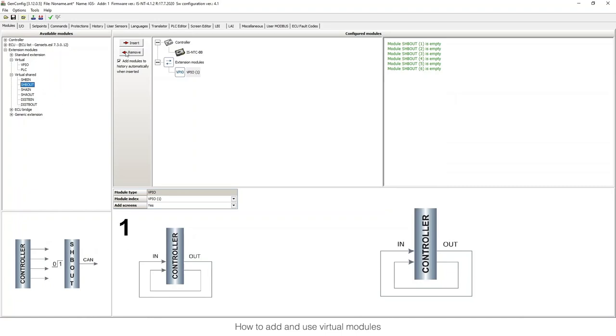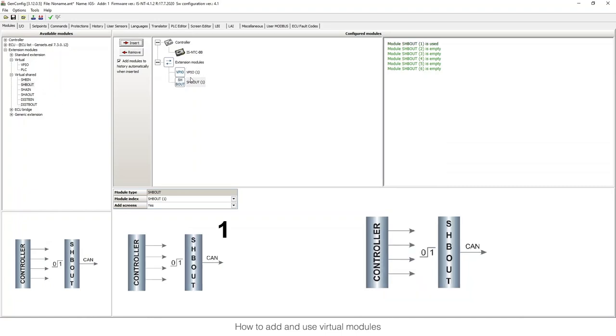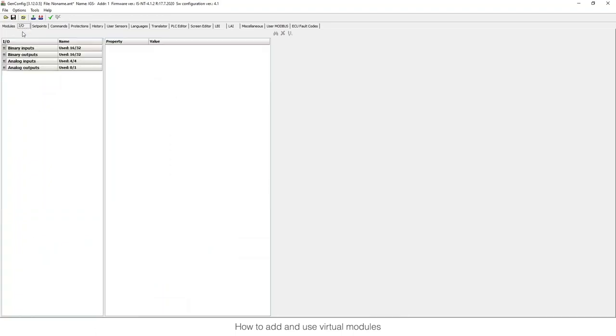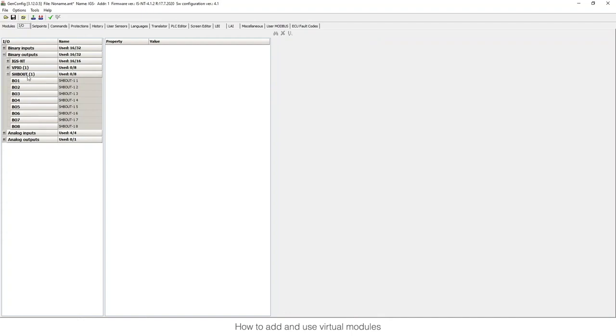When I choose a server binary output, I am sharing information from this controller to another controller. I configure the server binary output with index one, and it will be read by another controller that has the server binary input with index one — it is important that both have the same index. So in the first controller I connect server binary output one, and in the second controller I connect server binary input one to receive the information.